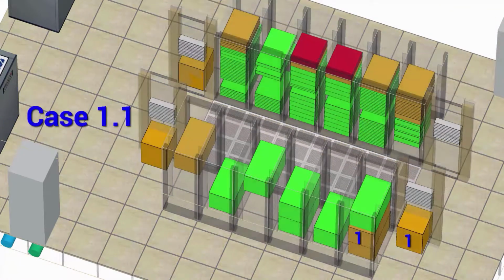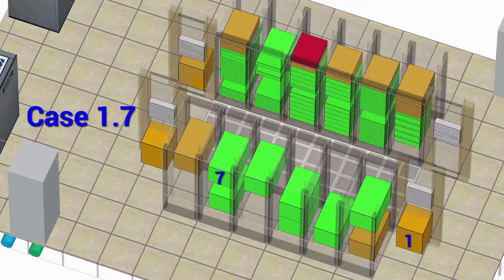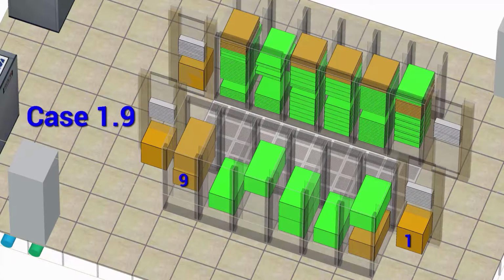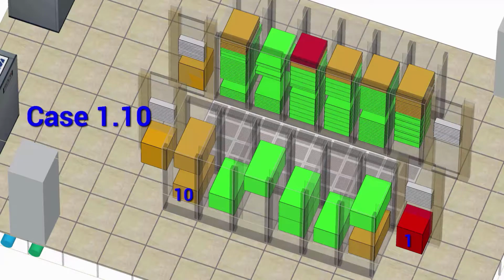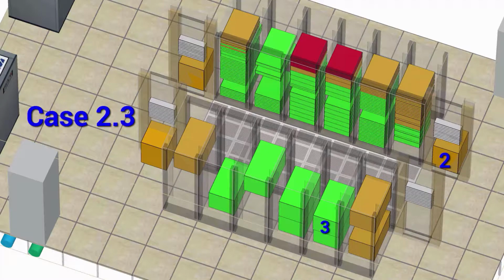The simulation results of the 20 different models are shown by colouring each piece of IT equipment based on the recommended ASHRAE inlet temperature. Equipment coloured green is in the ASHRAE recommended temperature range, orange is in the allowable range, and red is outside of the ASHRAE allowable range. Demonstrated by the simulation results, changing the location of the blade chassis and network switch has an impact on the data center environment as well as on the previously installed IT equipment.